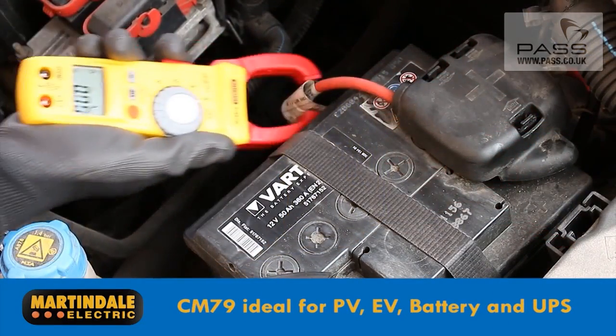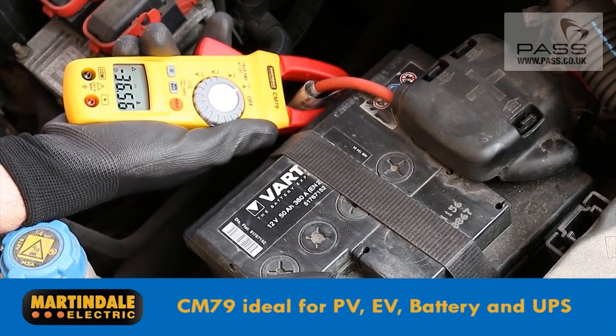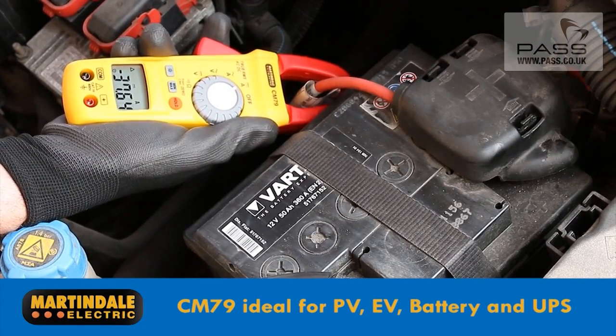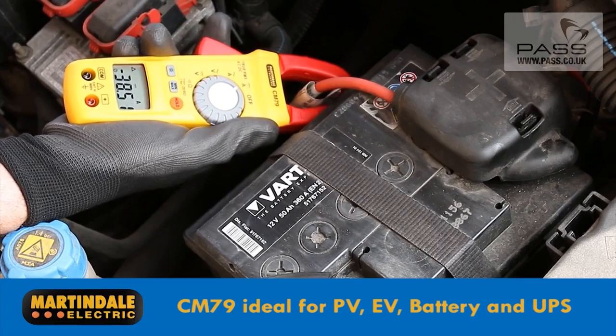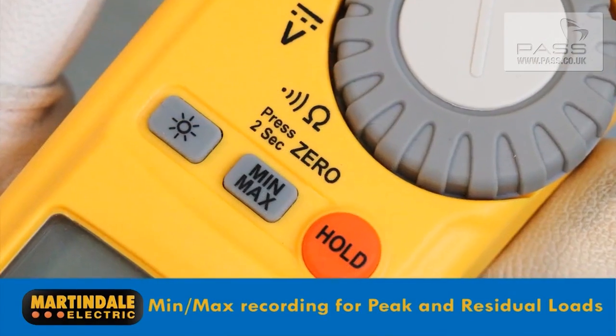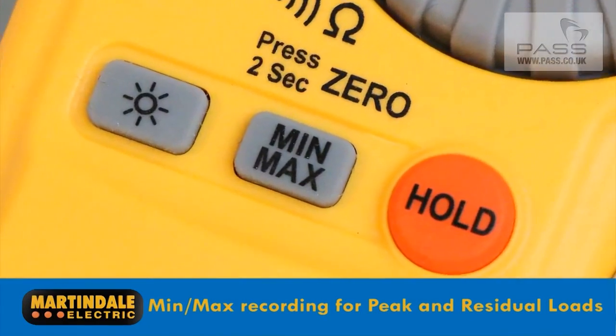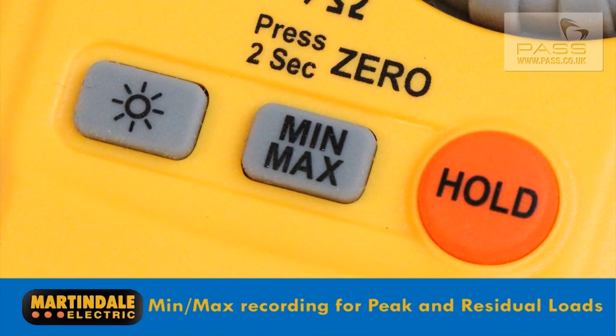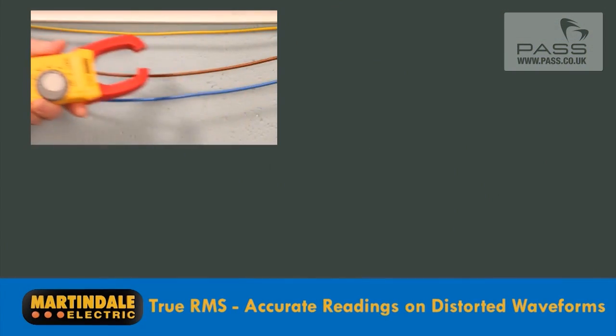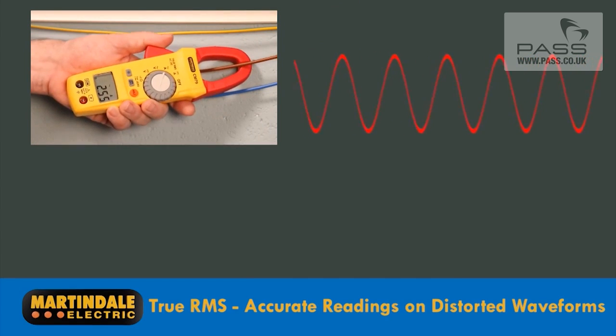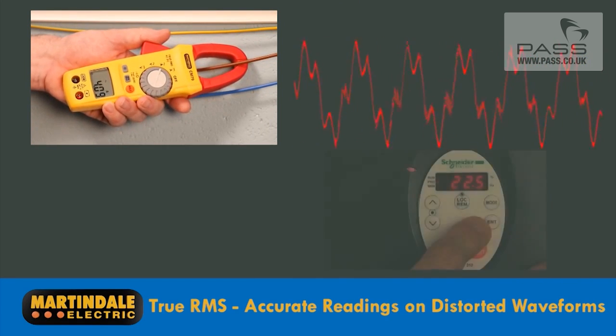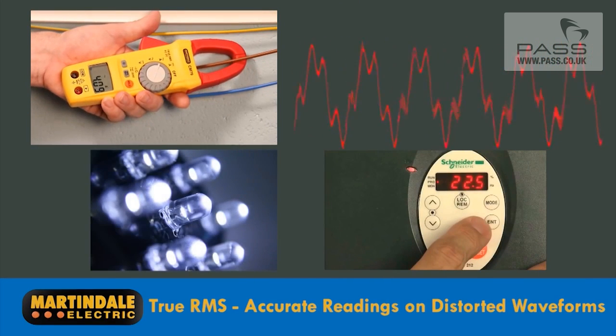The AC-DC capability of the CM79 makes it ideal for solar power installations, electric vehicles, battery testing and UPS systems. Additional features like min-max recording are useful for troubleshooting peak and residual loads. Being True RMS means you get very accurate, reliable readings with distorted waveforms, caused by electronic controls for motor drives and lighting.